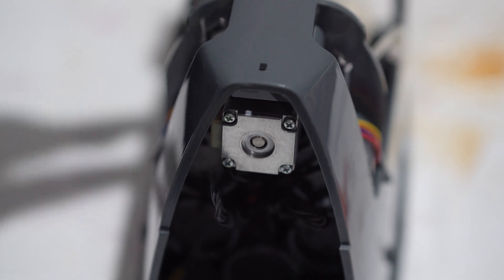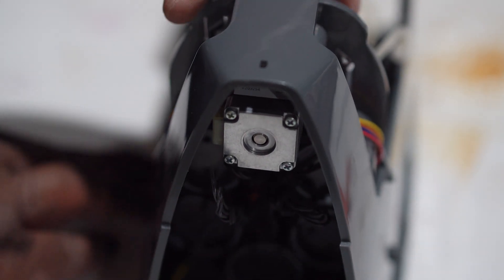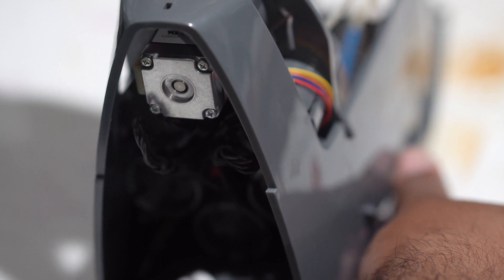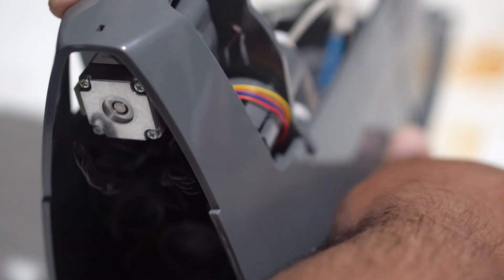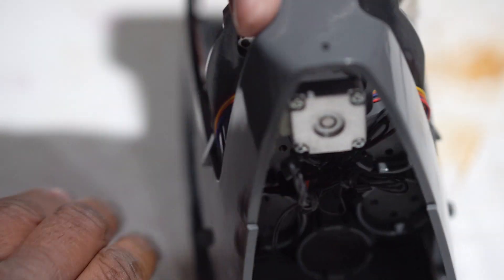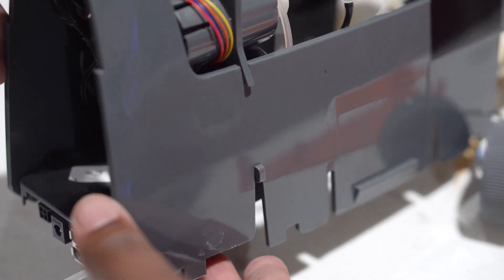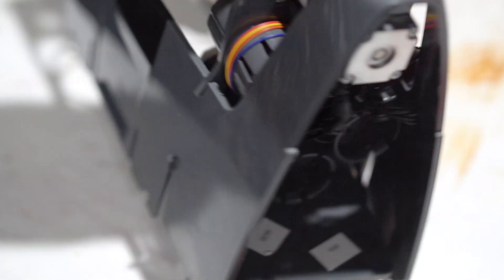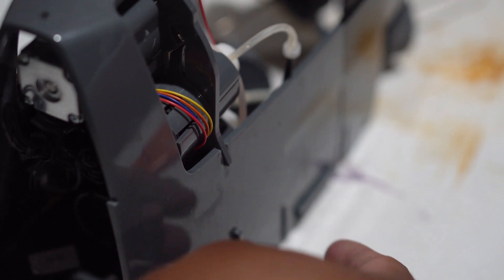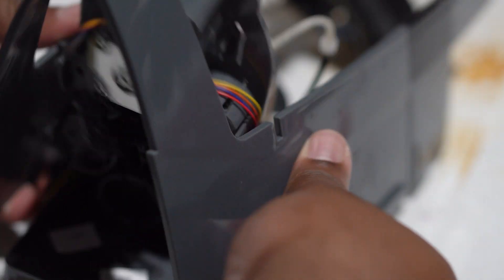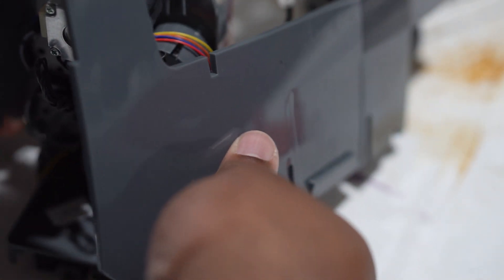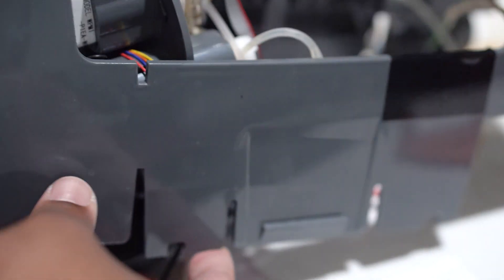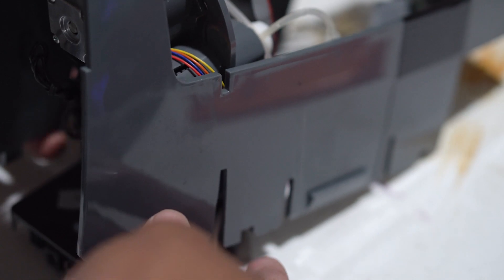After you've done this, the next step is to separate the upper sub-cage from the pump head guides by gently pulling the cage away from the tabs to separate the lower cage. Basically this thing comes apart in about 50 million little pieces. However, it's really easy and really simple and they all have guidelines in order to guide you along the way. Once you've removed that upper cage, the dosing tube heads should be a little bit loose. You should be able to gain access to all of the internal components of the Trident, and now we can actually start our repair.